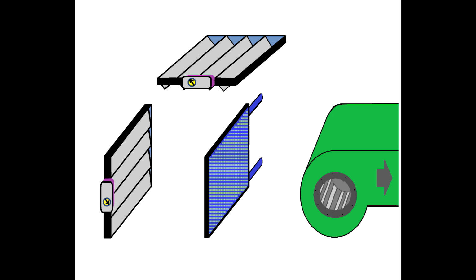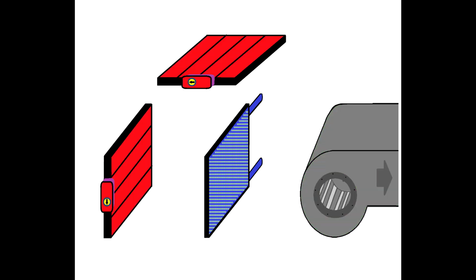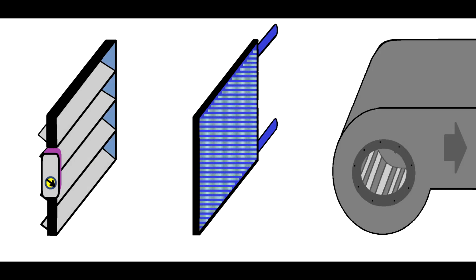This motor uses two dampers, and the dampers are usually interlocked with the motor. I want to show you a different type of integration and a different type of arrangement. Like you'll see in this movie, this motor can get air from one or the other damper. They don't need a functional interlock, they need only a safety interlock. If one damper is broken and cannot open and the other one is also closed, the motor will be like a blocked vacuum cleaner. It couldn't drag air and it will burn. That's why we interlock the dampers.